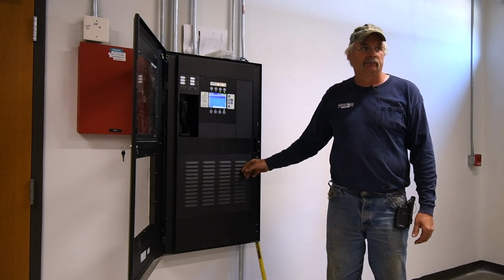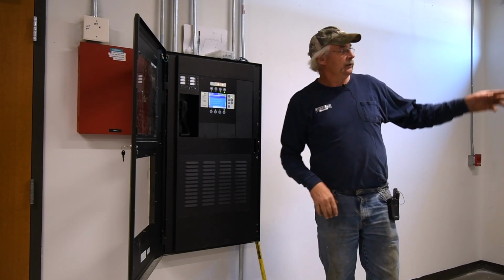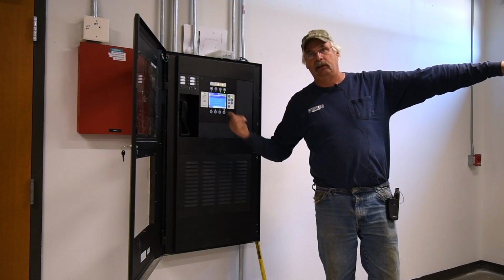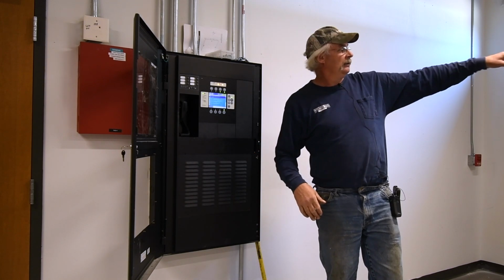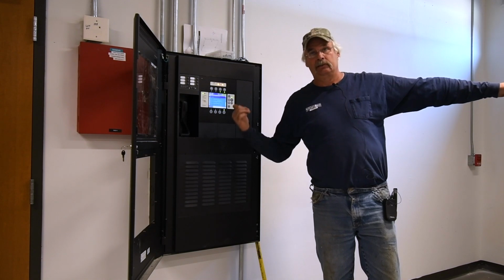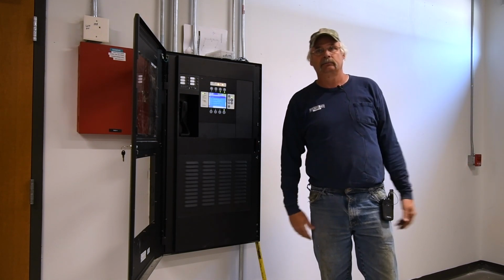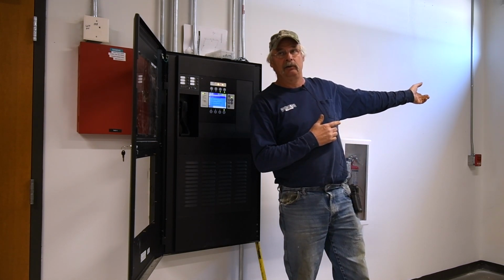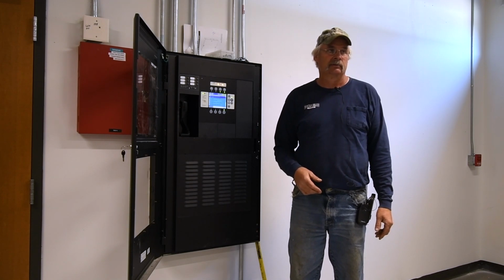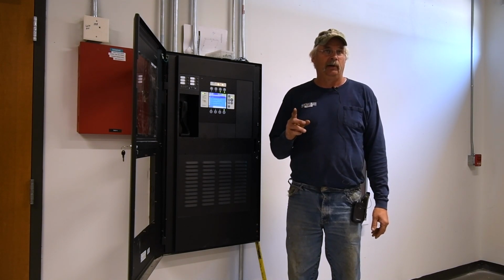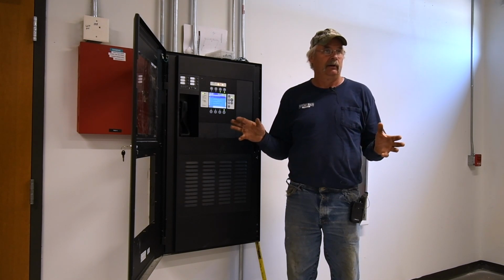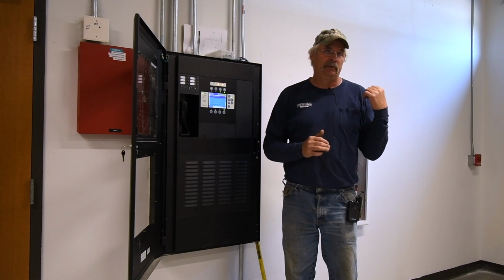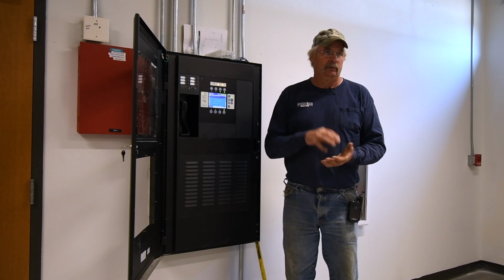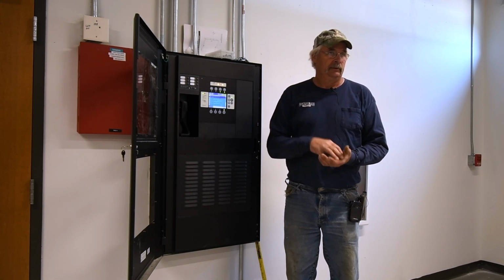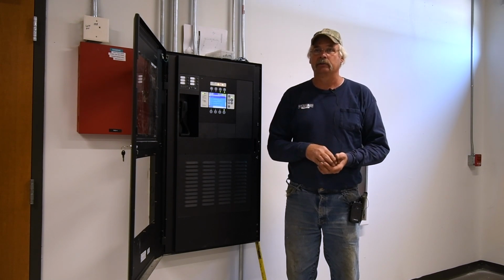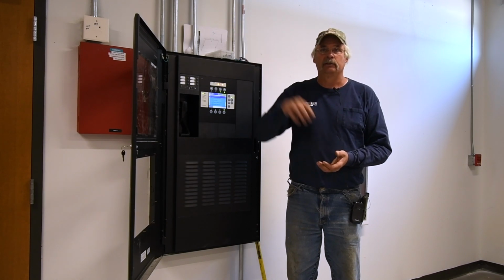So this panel will pick up all your different devices. If you have a flow switch go off on your wet system in the north mechanical, it's going to say high school north mechanical. If you have an alarm go off on your dry system, it's going to say North High School Mechanical. If you have a flow switch go off in the pump house, it's going to refer us to the high school pump house. Once we get done here, there'll be one fire pump that feeds all the different facilities. The new fire pump and the new fire pump house will take on the new high school, the existing school, the gymnasium, the bus garage, and the maintenance shop.